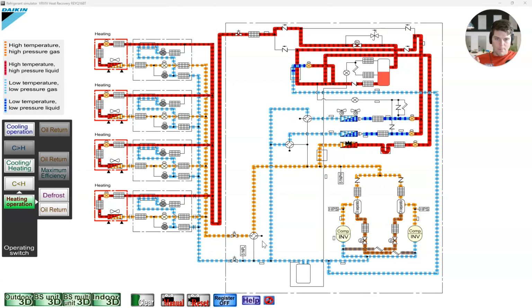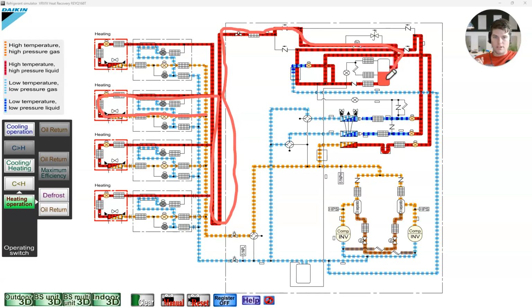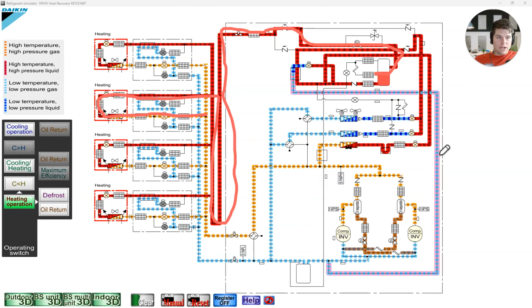When we talk about heating operation, we know that hot gas comes into the coil, creates liquid, then that liquid comes down and takes a nice little loop-de-loop around the system. It comes in and goes right to my liquid receiver. Where am I checking subcooling?